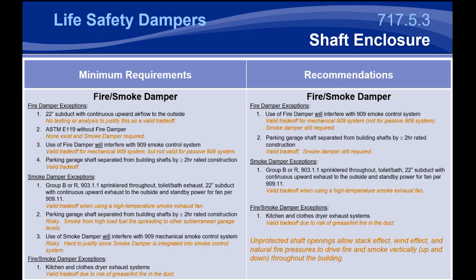and affect areas down below, where the smoke won't naturally ventilate out of the building. There was a code official, a fire marshal, that was in a fire where it was kept to one story, so it didn't actually spread through multiple stories, but there was a failure in the sprinkler system, and there was no backup power generation for the exhaust shaft. So the fire was contained in one story, but they actually had smoke damage on the story below the event of a fire. They had used that subduct as an exception, and the smoke actually cooled and was pulled down that shaft. So if you don't have constant airflow or high temperature fans that are pulling that smoke out of the system, it is a bit risky to remove your smoke damper, because that smoke will get in the shaft and it could be pulled down to a non-affected area.